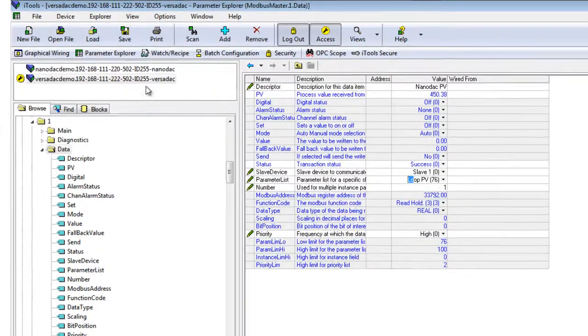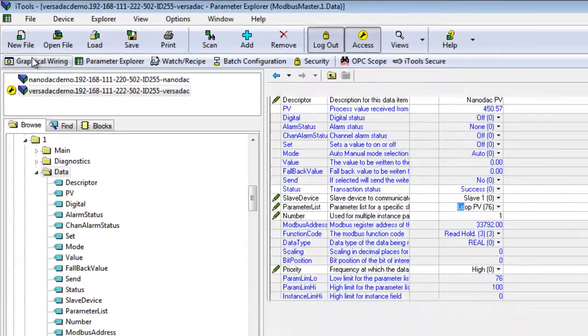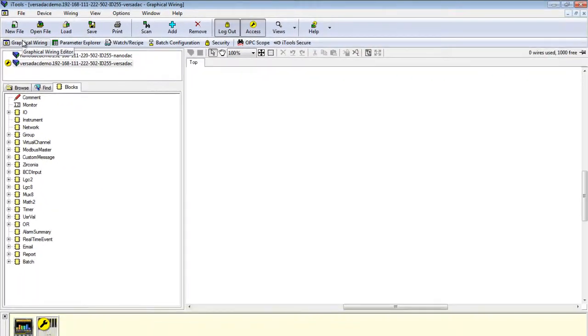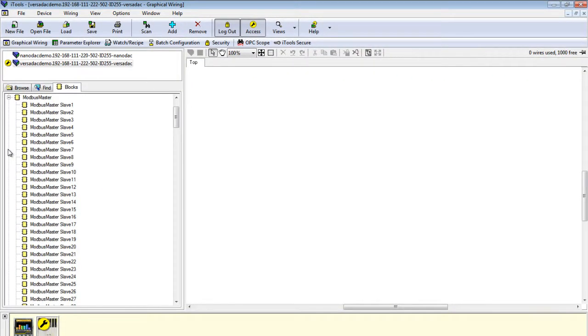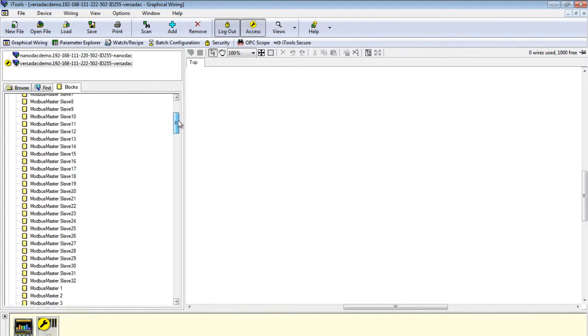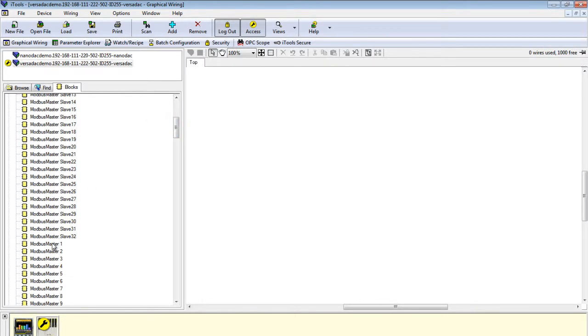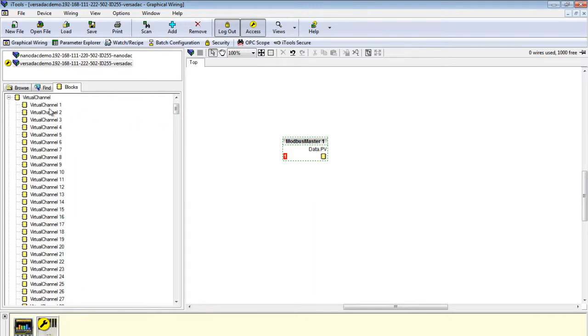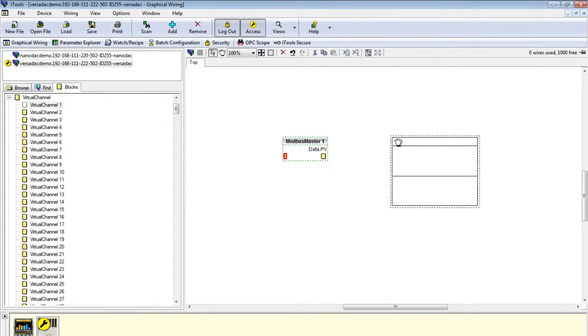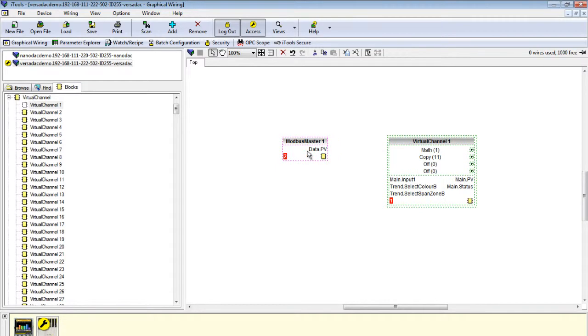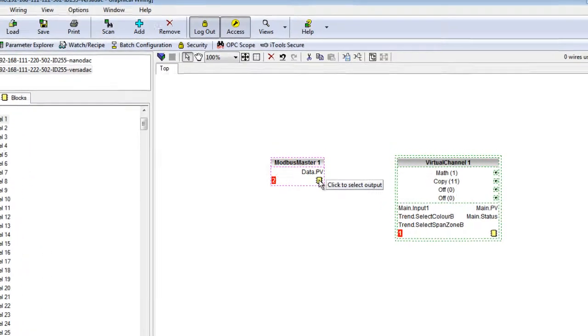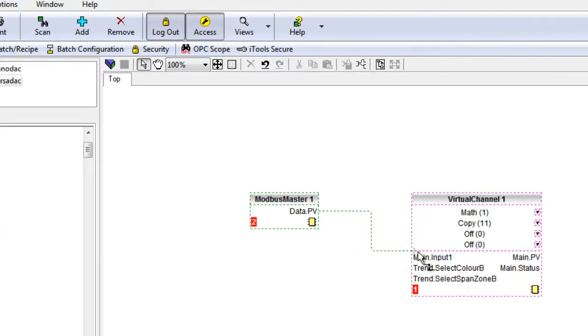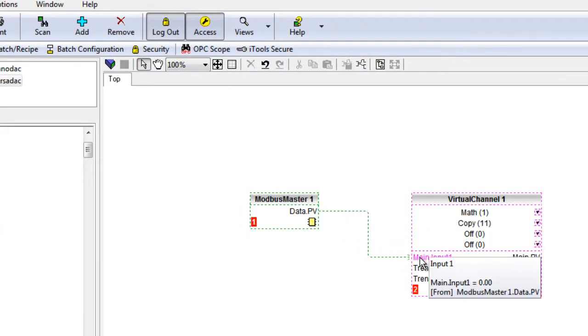Select Graphical Wiring. Drag Modbus Master 1 into the Wiring panel and also select Virtual Channel 1 and drag onto the page. Click on the Wiring icon at the bottom right of the block. Select PV and drag to connect to Main Input 1.